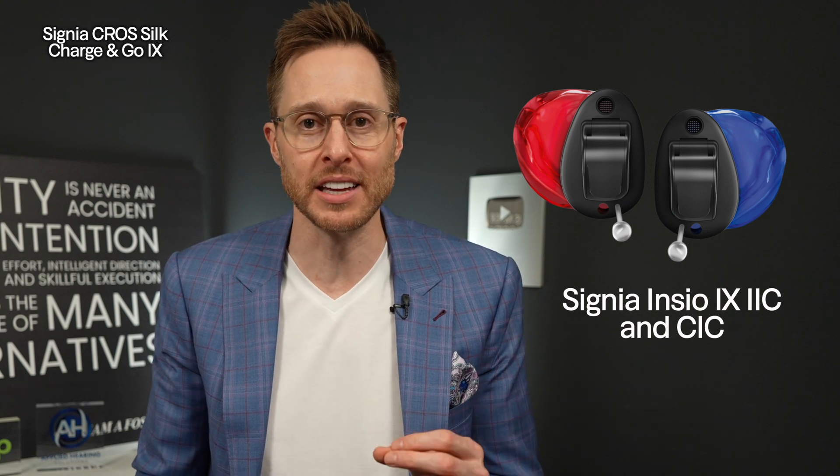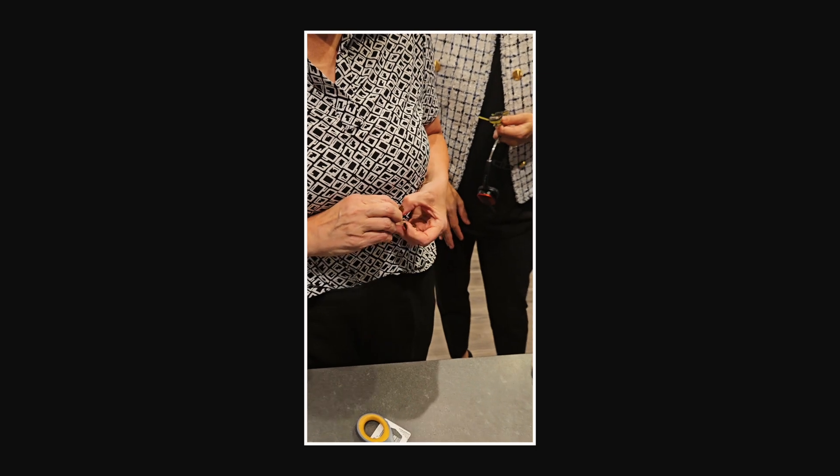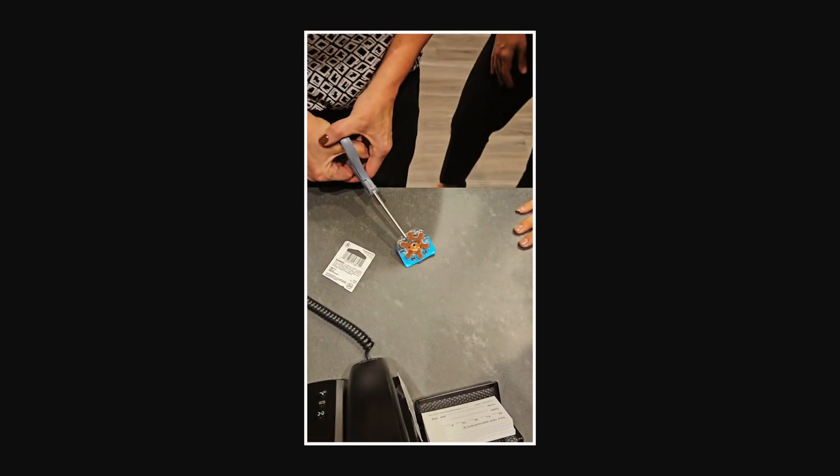Not only is the CROS Silk device compatible with the Signia Silk Charge & Go iX, but it is also compatible with the invisible-in-the-canal and completely-in-the-canal version of the Insio iX. The Charge & Go part of its name means that this CROS transmitter is rechargeable. Previous generations of this Signia Silk CROS transmitter used a size 10 disposable battery, but they have gotten away from disposable batteries — and just in the nick of time, because new battery packaging laws make it very difficult to use disposable batteries anymore. Programming and verifying the programming of this CROS transmitter is very difficult to do, but once you get it done and get it done well, the performance of this tiny little device is pretty impressive.